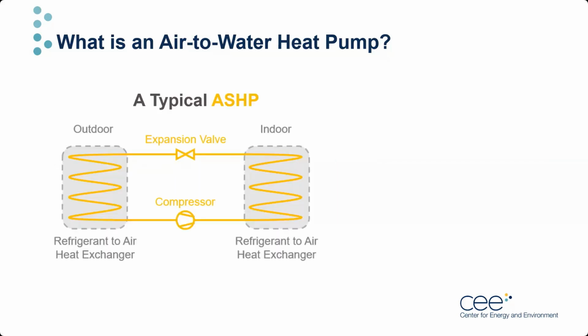So here we have a typical air-to-air ASHP at its core. The refrigerant loop here is shown in yellow. It has an outdoor unit with a refrigerant-to-air heat exchanger, expansion device, and compressor. Indoors, the cycle is completed by another refrigerant-to-air heat exchanger that releases the heat into air distribution systems like ductwork when in heating mode. Now let's take a mental snapshot of this diagram before we look at how much of this changes with an air-to-water system on the next slide.